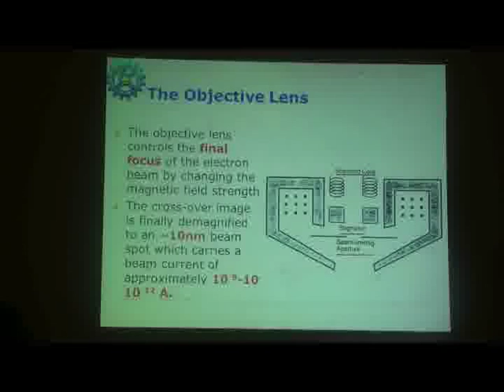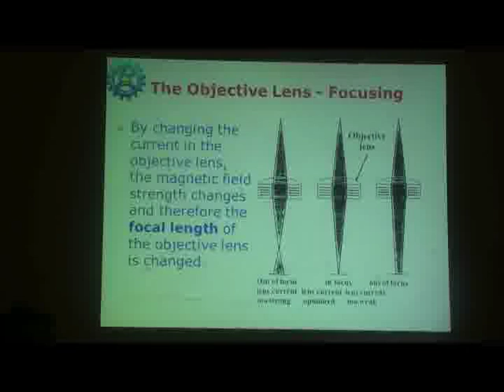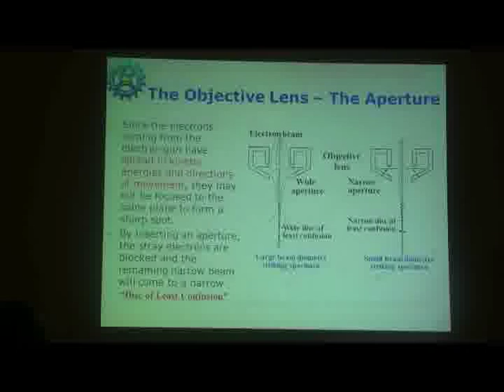You can change the objective lens excitation: more current, less current, and high current. So there is out of focus, in focus, and out of focus again, where the lens current is too strong before reaching the sample area. Of course, these are fine details which you may not require right now. I just give some glimpses of what you will use when you are really using the electron microscope.